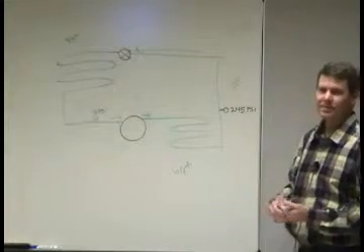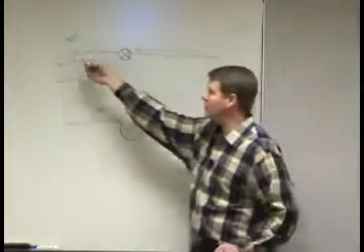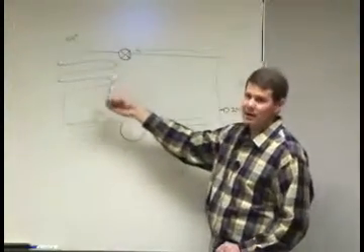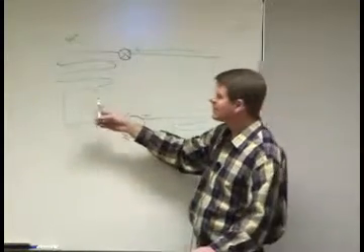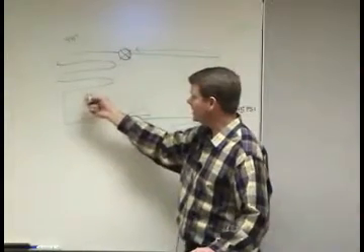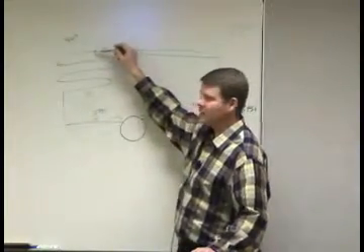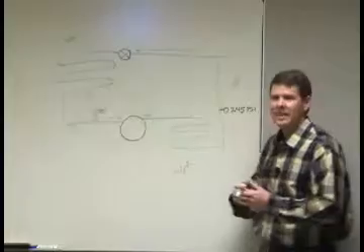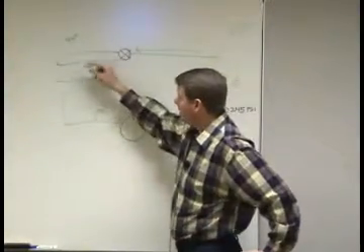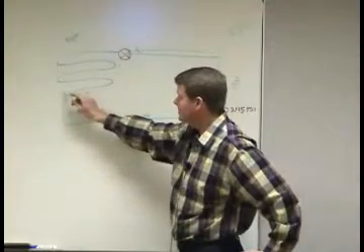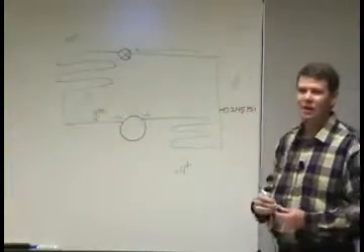It's going to boil back off, because all it needs to be is 44 degrees to boil, and we got 75, so that's a pretty good heat source. So now this air coming across that coil adds heat to that liquid. That liquid then boils off, and when we get down to the end of the coil, hopefully we've got vapor again and no more liquid.